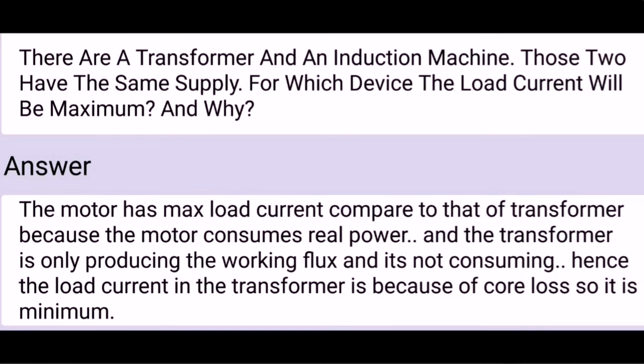There is a transformer and an induction machine. Those two have the same supply. For which device will the load current be maximum, and why? The motor has maximum load current compared to that of the transformer, because the motor consumes real power, whereas the transformer is only producing the working flux and not consuming real power. Hence the load current in the transformer is due to core losses, so it is minimum.